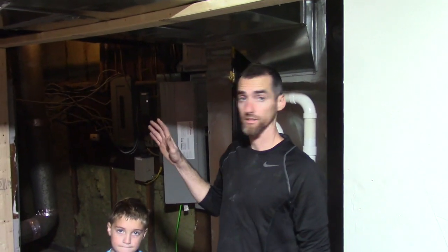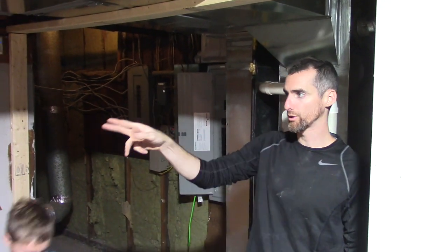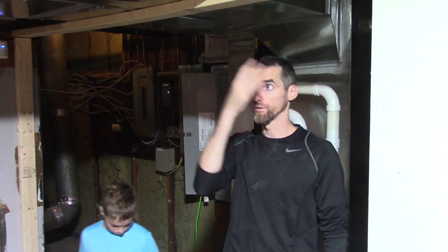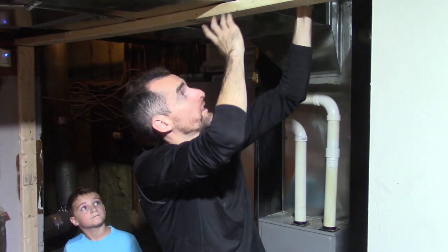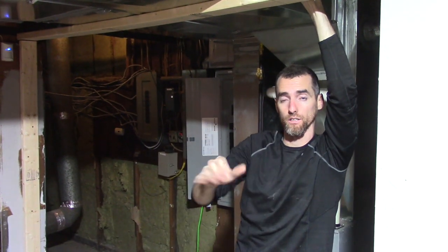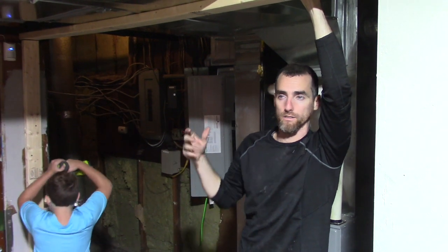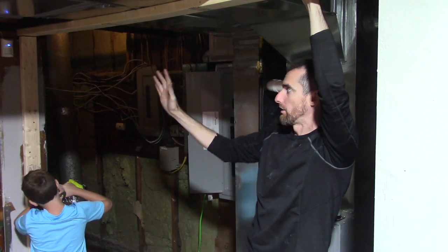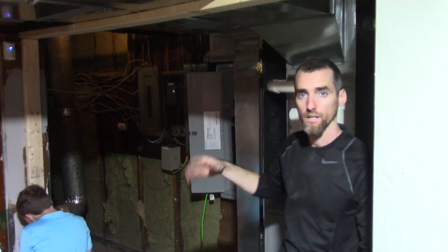All right, we're building the wall. We're going to have a door for behind the dryers. We're going to end up probably moving the change machines over here. I'll show you a video of inside the laundromat where we think it's going to be a better spot. But we're going to have this walled in. We're going to have to do some goofy wall up here over all these wires and all the things. That way, the air behind the dryers is different than the air out here. We don't want the air going to the dryers from our heated air or our AC air. We want it to be from outside air. That way, the makeup air is coming directly from outside. So we'll have this all insulated, and it's going to be a different temperature back here and out in the laundromat.